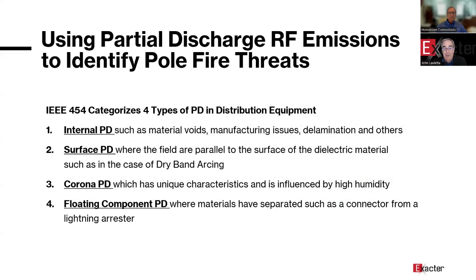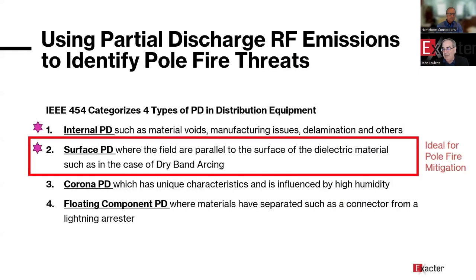So IEEE defines partial discharge, the thing we measure, as 4 different types. The first is internal PD, and that's basically manufacturing problems or problems that have come from wear and tear. The next is surface PD, where contamination has gotten on the outside of insulators or any device, bushings, lightning arresters, combo units, all the equipment that has insulating properties that are exposed.